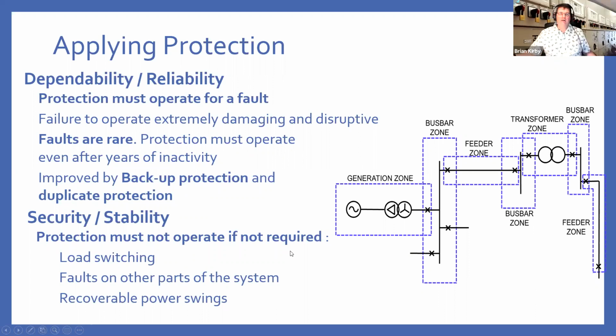Dependability and reliability are one balancing act you have to do when you're designing your protection scheme, because your protection must operate if there's a fault, because failure to operate is going to do lots of damage. But faults are very rare, so your protection could sit on a part of the power system and not see any faults for decades. But when a fault does occur, it must operate. The use of backup protection and duplication helps with this. Another thing that most modern power system protection devices do is they have self-testing facilities, so they can internally check that everything is still operating as you would expect while the power system is still energized.